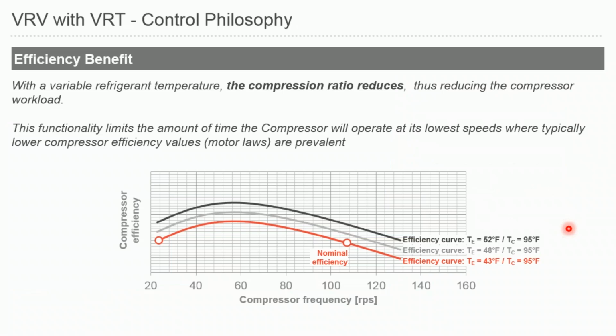Again, most of you are familiar with VRT technology. We've been using this with our own VRV product since 2014, and the way it works is basically changing the target evaporating and condensing temperatures depending on the operation mode that your unit is running in. And you also have your inverter compressors, and at partial loads, reducing the compressor frequency to a certain extent is really important.